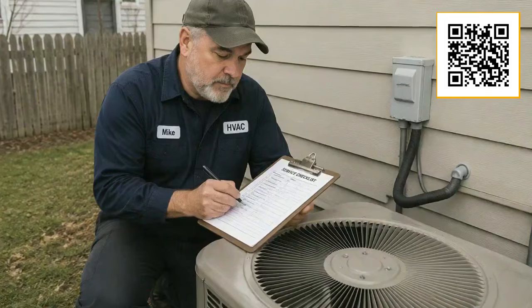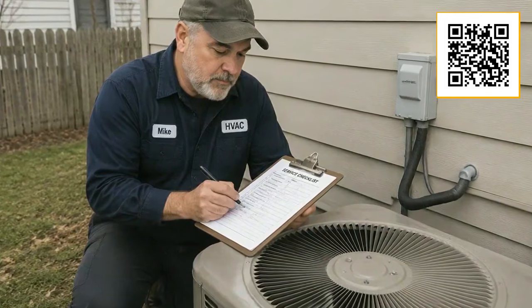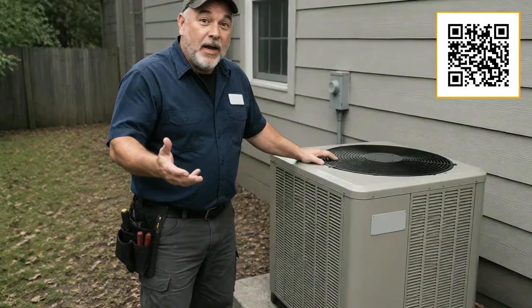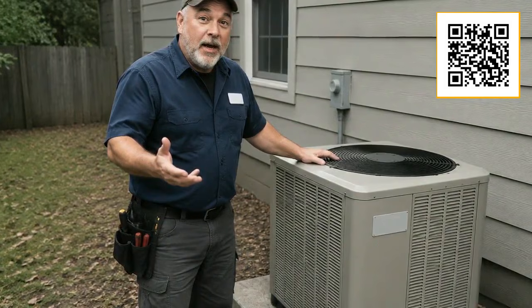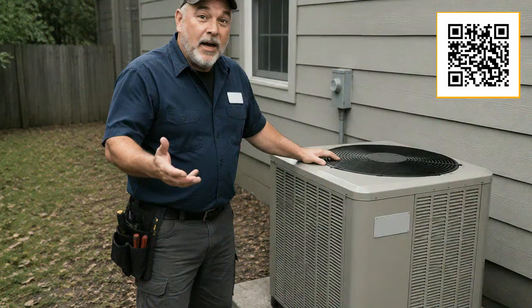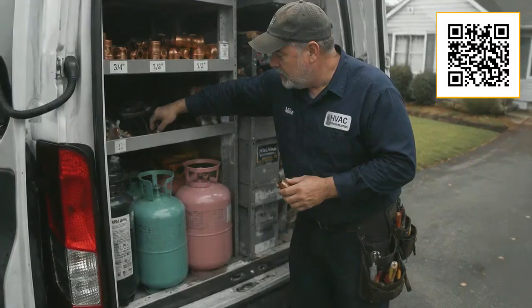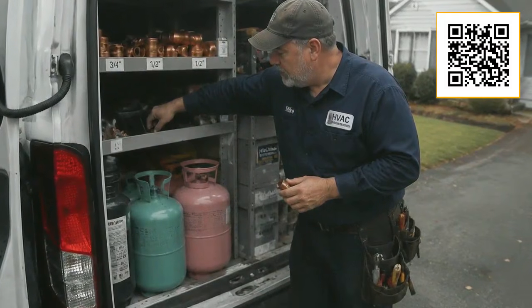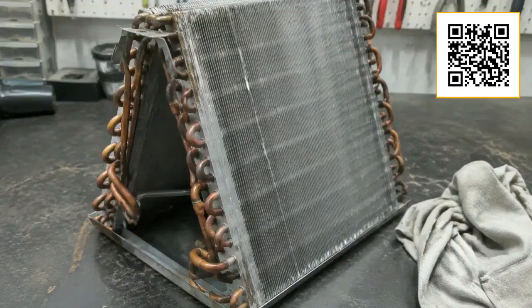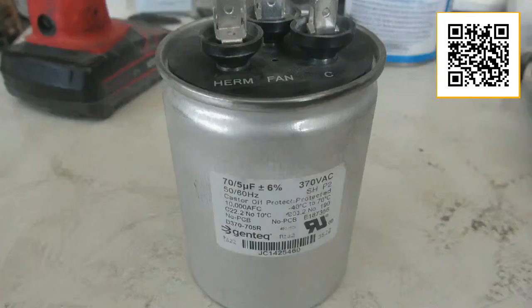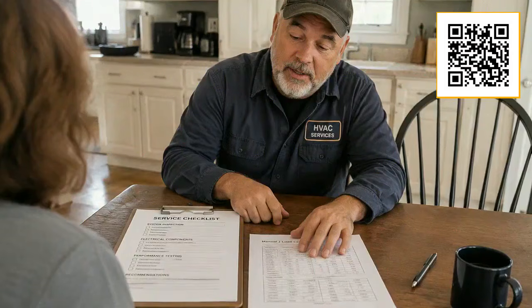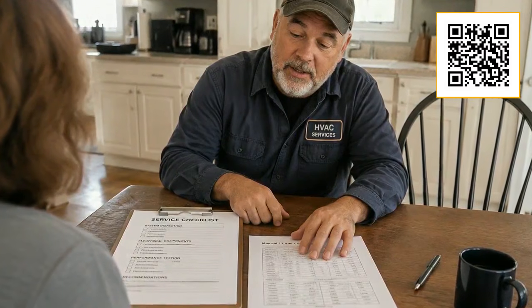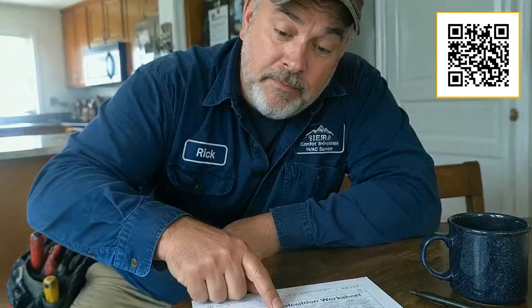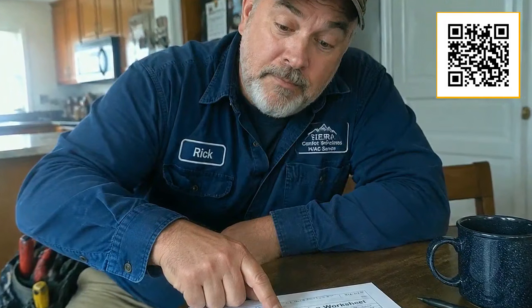None of those failures are mysterious. They are all predictable, and most of them are either avoidable entirely or at least manageable if you catch the warning signs early. The plain action plan is this. This week, find your unit's nameplate and write down the brand, model, refrigerant type, and installation year. This month, schedule a spring service if you have not had one in the past year, and ask the technician specifically about the evaporator coil, the capacitor, and the refrigerant level. Before your next unit purchase, get a written load calculation from any contractor who quotes you, and do not let someone talk you into a bigger unit without showing their work.